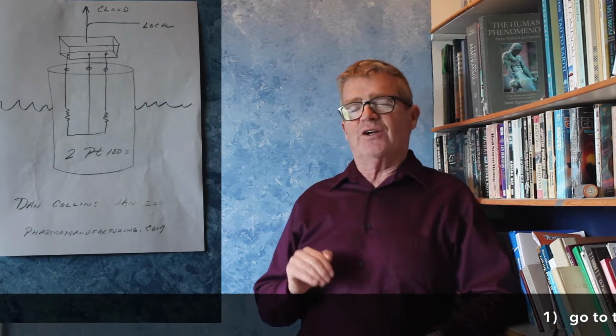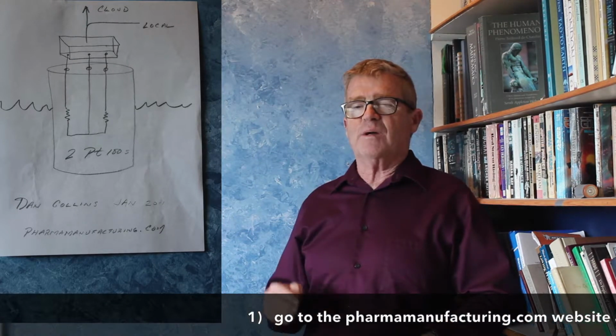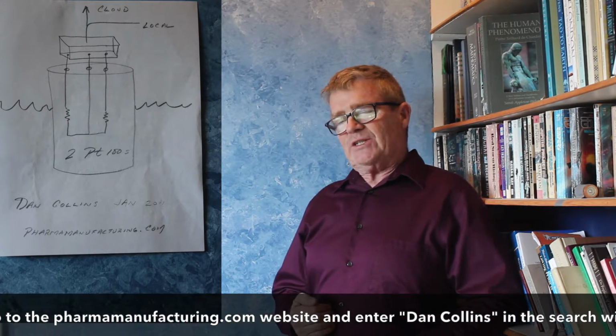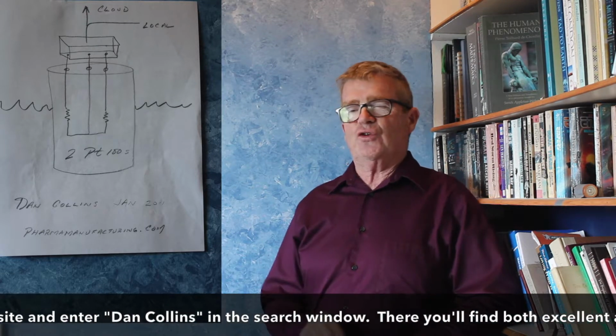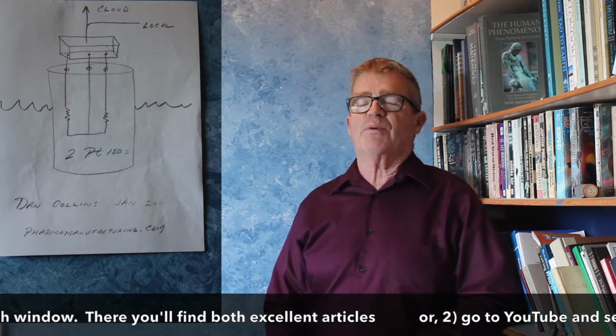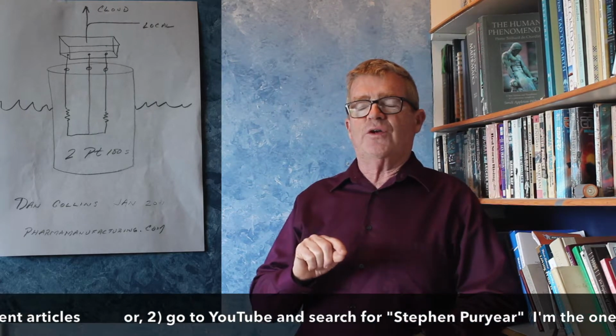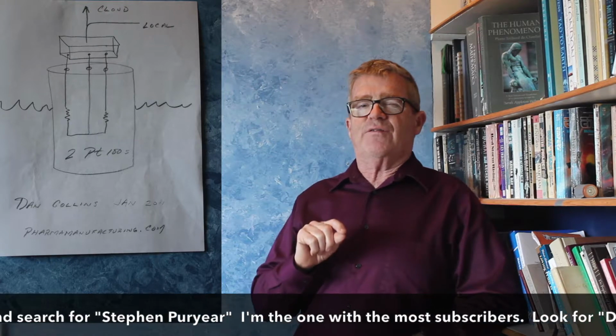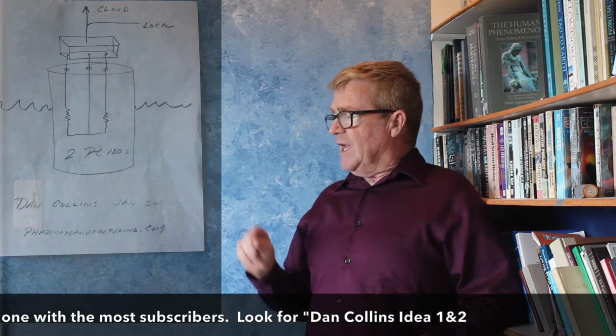Now, I don't need credit for this idea because it came from Dan Collins in an article he wrote in 2011 in Pharma Manufacturing magazine. Essentially, in the terms we're using today, he said put 2 PT100s in the same probe, put it in the process, and then use each PT100 to monitor the performance of the other device. As long as they agree, you're cool. If one starts to drift, you use the other PT100 to detect it. Dan made his argument using Monte Carlo simulation and control charts, but he convinced me that theoretically he had a way to detect calibration drift long before the device went out of tolerance.